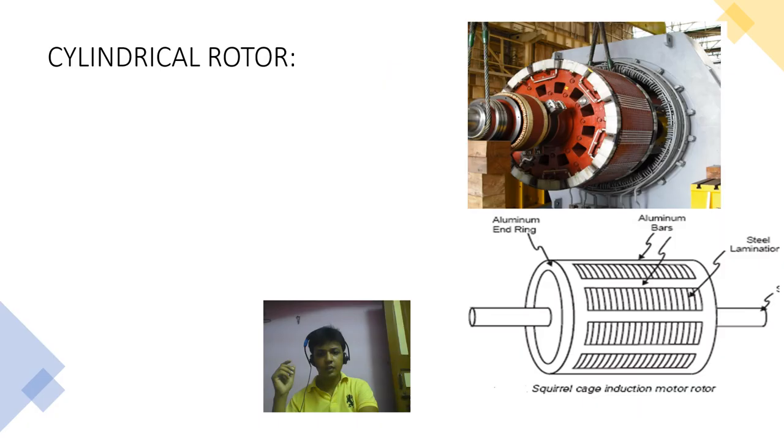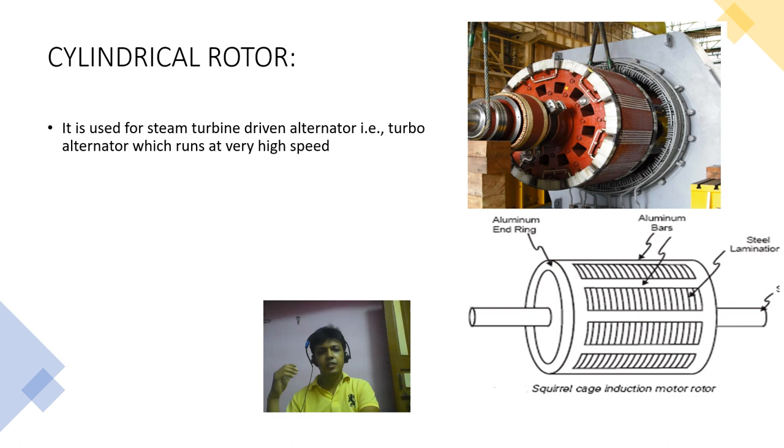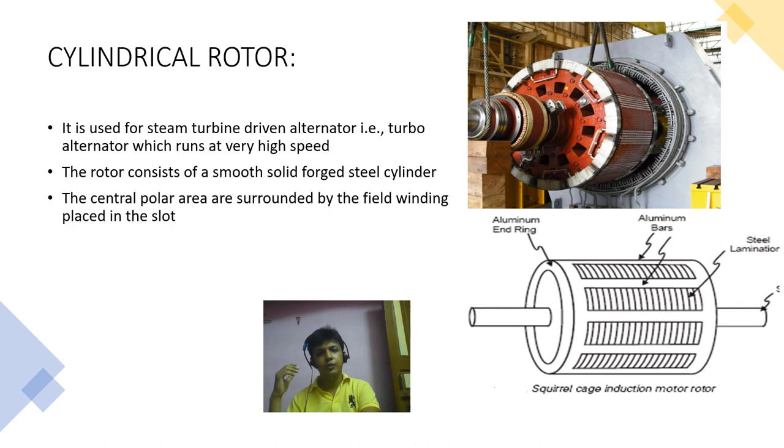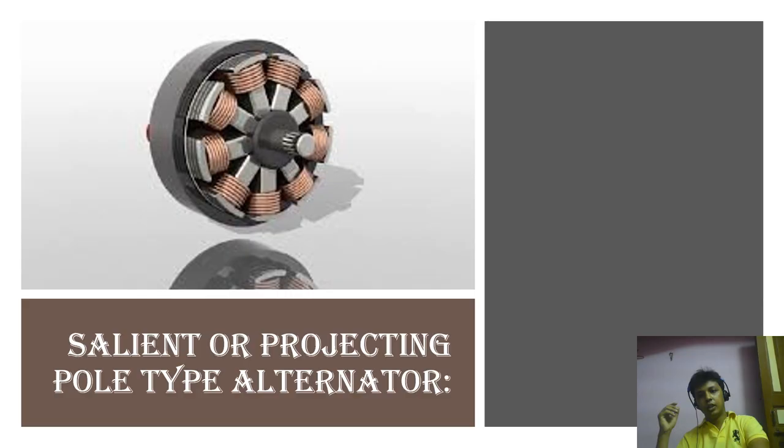Now we are going to discuss about cylindrical rotor. It is used for steam turbine driven alternator, that is turbo alternator, which runs at very high speed because it has less number of pole. And we know that speed equal to 120 f by p. As the number of pole is less, speed is high. The rotor consists of smooth solid forged steel cylinder. The central polar area surrounded by the field winding placed in the slot. To avoid excessive peripheral velocity, such rotor has small diameter and long axial length.